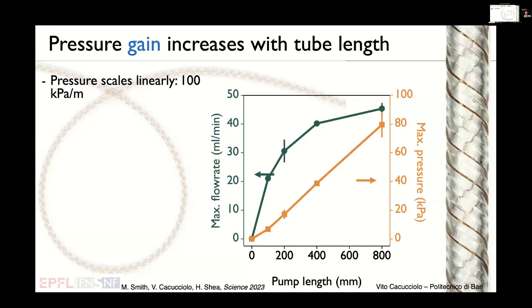In terms of performance, when we published in 2023, we could reach about 1 bar per meter of length of pump. The longer the pump, the more pressure you can get at the output. And again, this changed completely the way that hydraulics is designed. Generally, when you have a thin and long catheter and you want a certain output, you need to take into account all the pressure drop. The longer and thinner it is, the more pressure you need to apply from the outside to have the fluid move. This is a bottleneck for hydraulics, because generally you can't make very long and thin catheters and have a fast response at the output, because you would need an incredibly high pressure at the input that would actually blow up the tube. Here it's completely the opposite. The longer this is, the higher the pressure we can get at the output. And the flow rate, so the response, is actually independent of length.